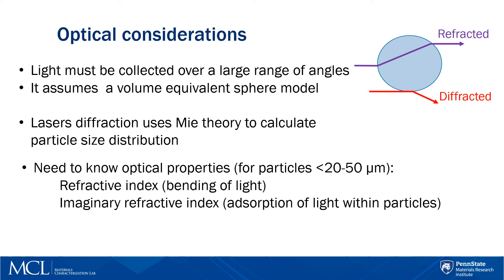Particles larger than this size provide useful information through diffraction but not refraction. This means we do not need the refractive index to accurately interpret the scattered light. For particles smaller than 20 microns, refracted light becomes increasingly important, and the choice of refractive index will directly affect accuracy in this size range.